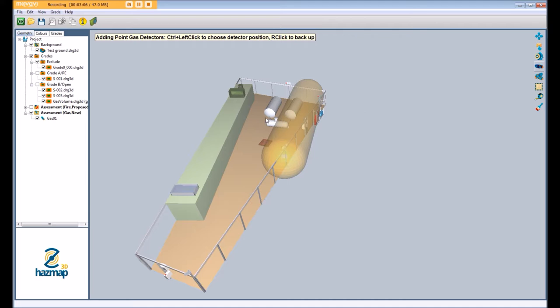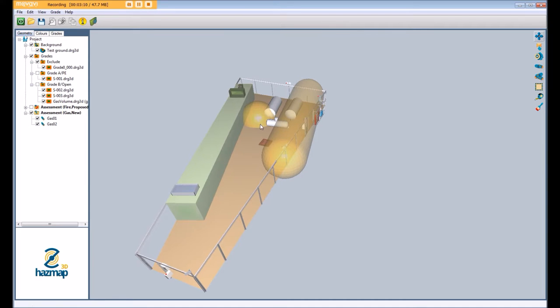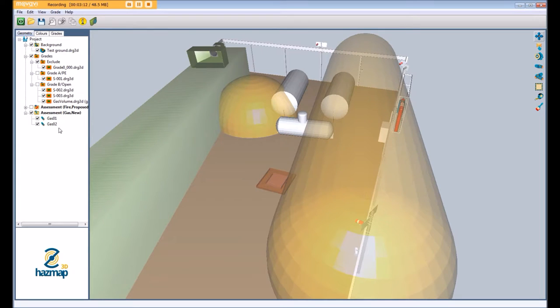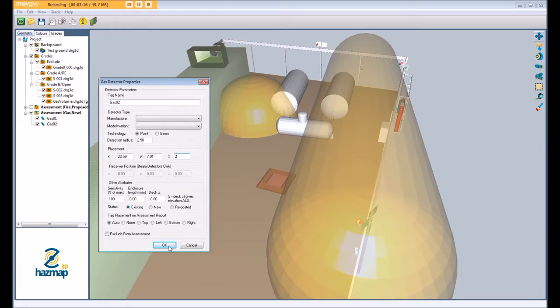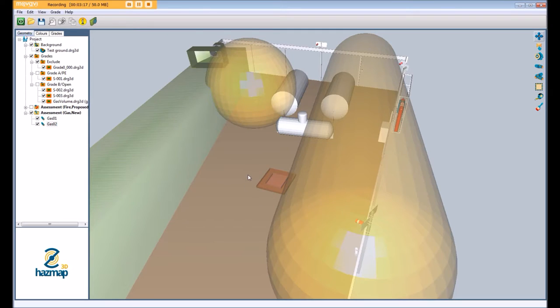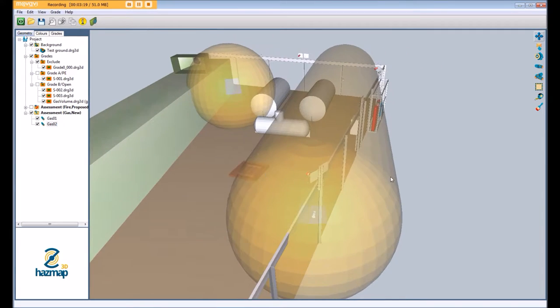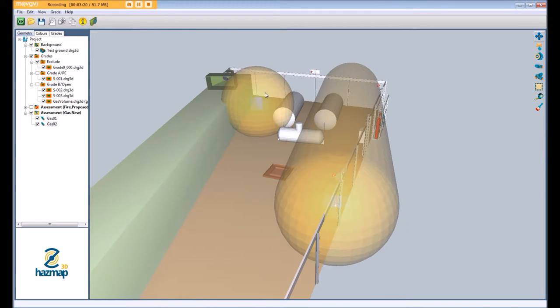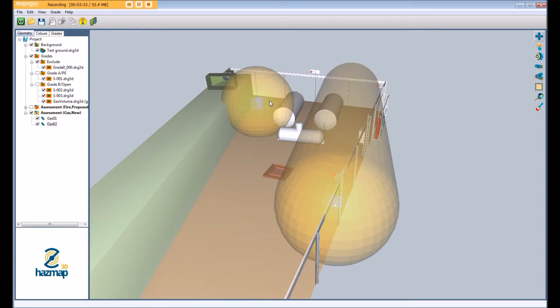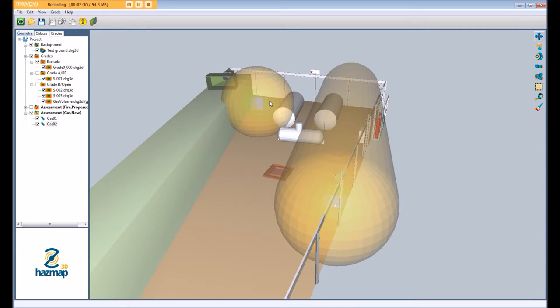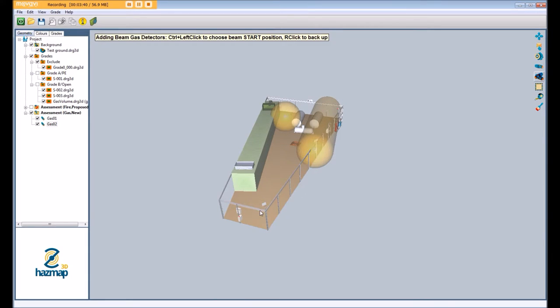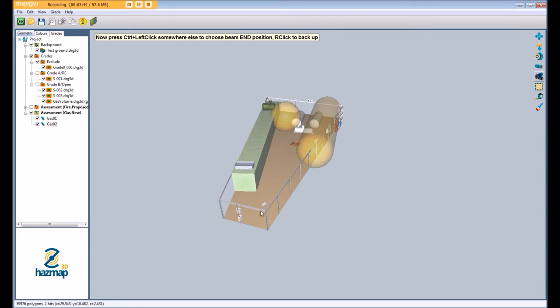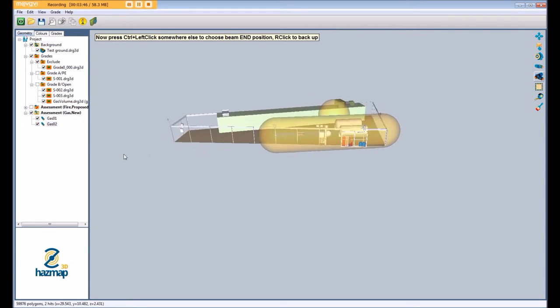I'm just going to add a point gas detector into this region here. Obviously we don't have a mounting bracket so I can just add the detector onto the ground and then increase its elevation by 2 meters. Now when the report is generated the software will recognize that there's no mounting location there for that device and that information will be generated in the report to explain to the engineer that a mounting bracket or mounting post will be required for that specific device with the specific tag, manufacture, model and all of that useful information. Now we're just going to add in a second open path which currently is not installed on the test ground but we will use that as a proposed device.